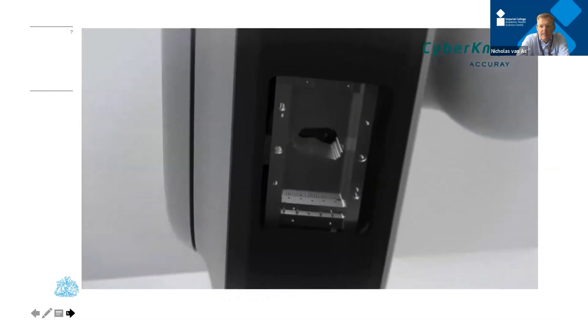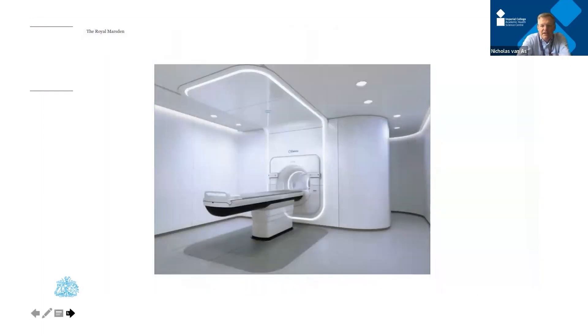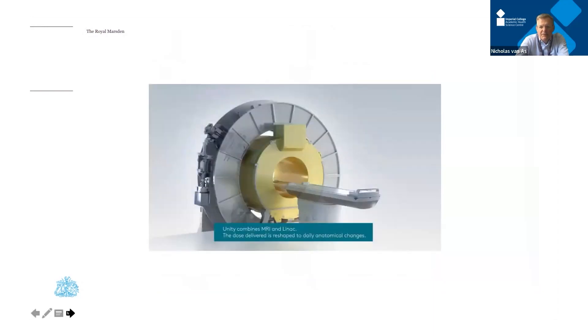The radiation beam tracks a lung cancer in real time and only delivers radiation when the tumor is in its path. A multi-leaf collimator, mounted in the head of the linear accelerator, allows the beam to be shaped in all different forms and sizes. The newest technology is a radiotherapy gantry with an MRI scanner mounted on the same gantry — extremely complicated physics, but it allows us to see in real time with MRI scans what we're treating and how it's responding.